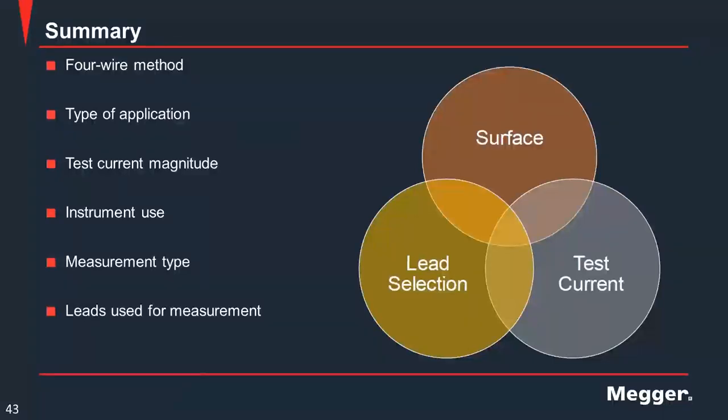Okay, let's go. The last slide is the summary. Low resistance measurement uses the four wire method. The key aspect of the four wire method is that the current lead and potential lead are decoupled from each other. You need to remember to keep them decoupled from each other, so you are eliminating any kind of lead resistance or contact probe resistance. We eliminate both by ensuring that you use separate leads.